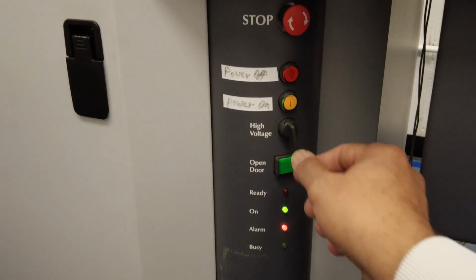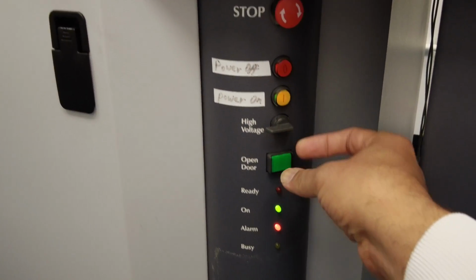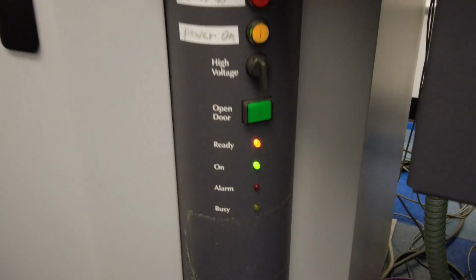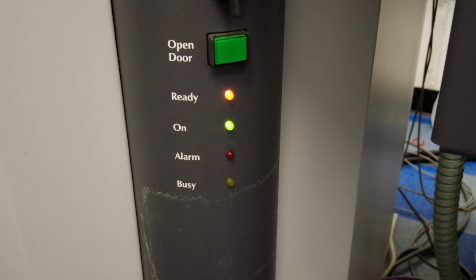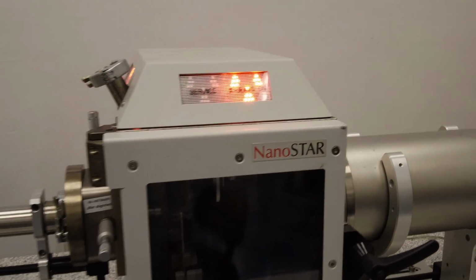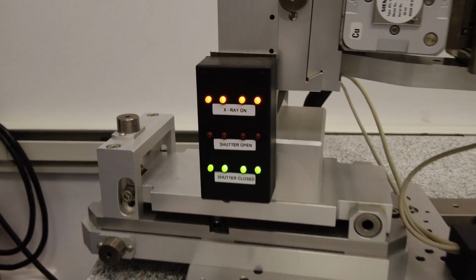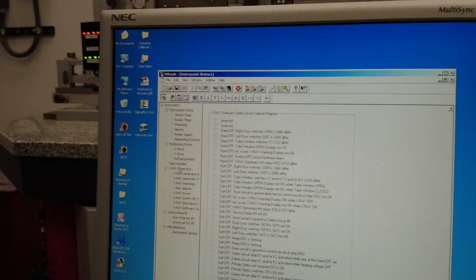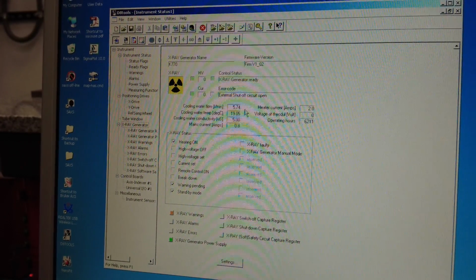Now the thing I wanted to specify here is that when I turn on the high voltage over here, the ready light turns on, alarm light starts to blink, and the X-ray comes on. So X-ray is on. I look at this sensor, it shows that the X-ray is on, and the alarm is blinking. So let me sit back for a minute. I look at the X-ray generator, and on the X-ray generator, now the cooling water flow is 5.74, cooling water temperature is 19, conductivity is as it is.